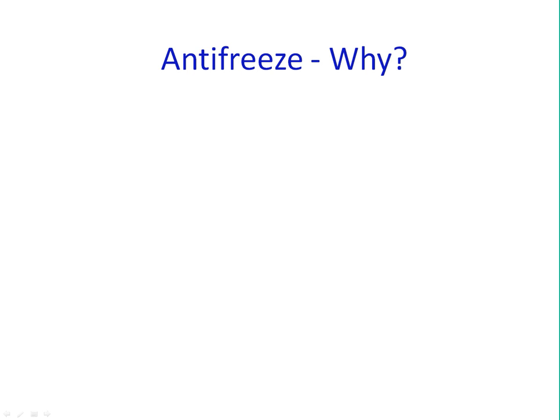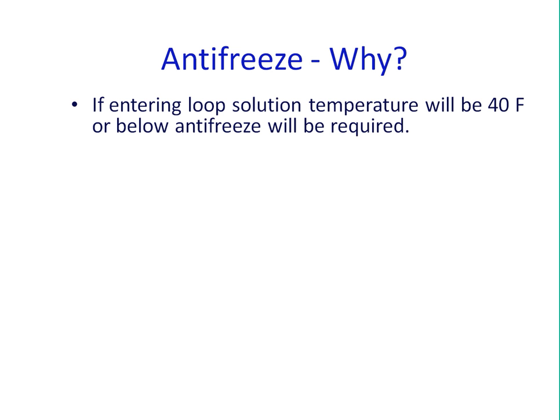We're going to start out by discussing antifreeze. Why antifreeze in a closed-loop system? Well, if your entering loop solution temperature will ever hit 40 degrees or perhaps below, then you're going to need to put antifreeze in there, because if it's entering at 40 degrees, it's going to be exiting somewhere around 6 to 8 degrees lower than that.